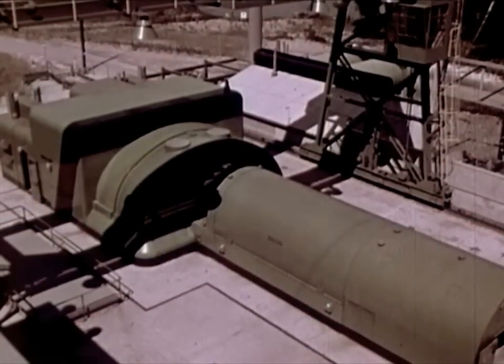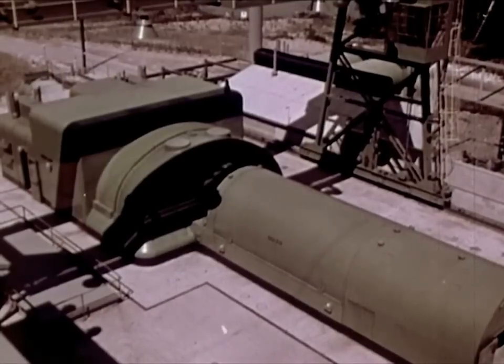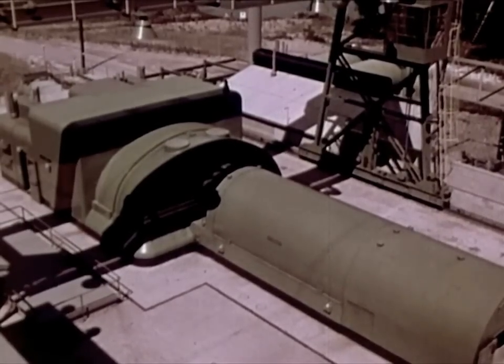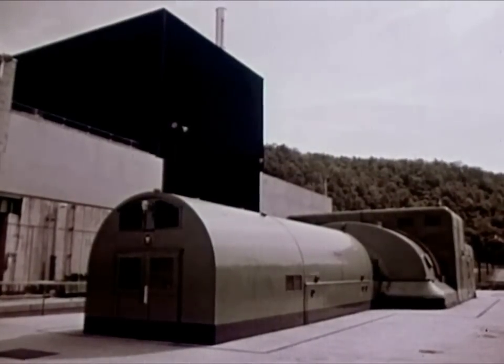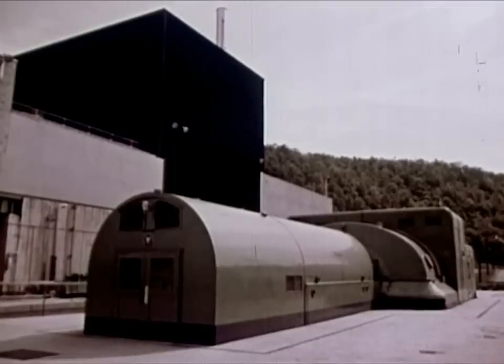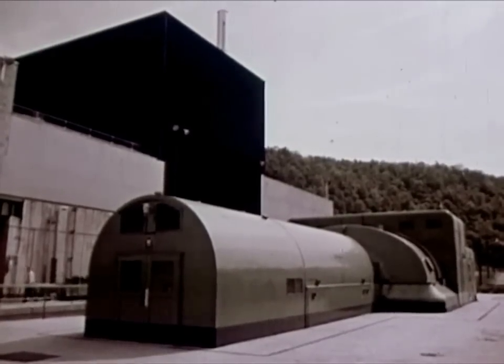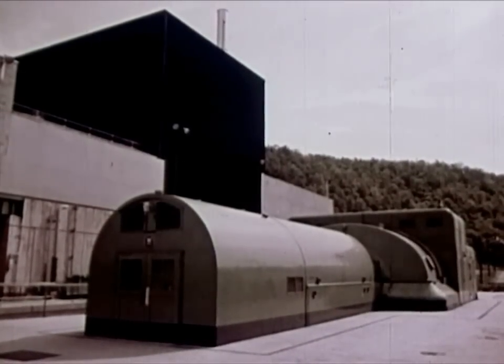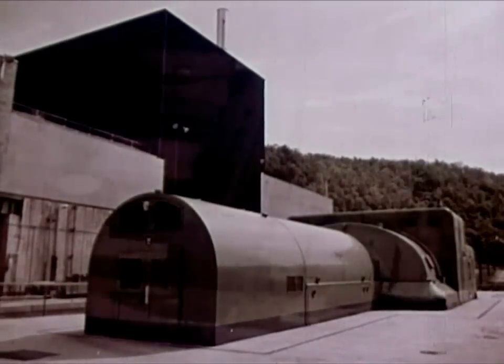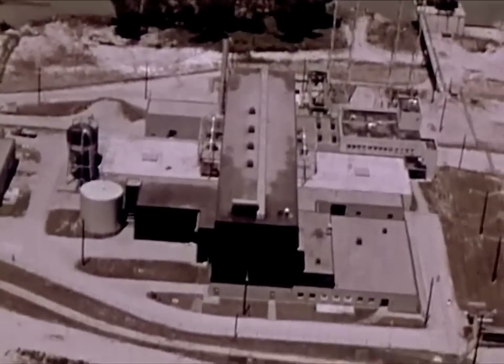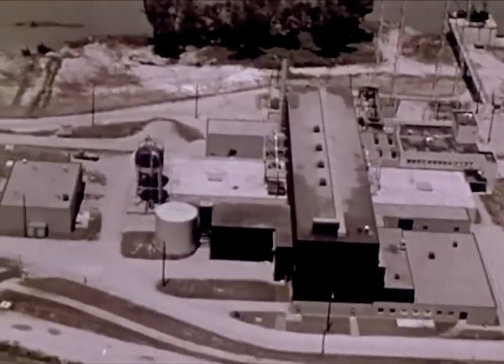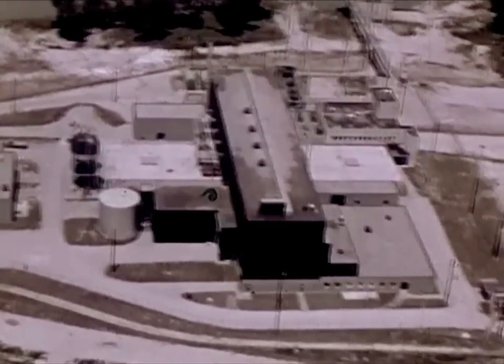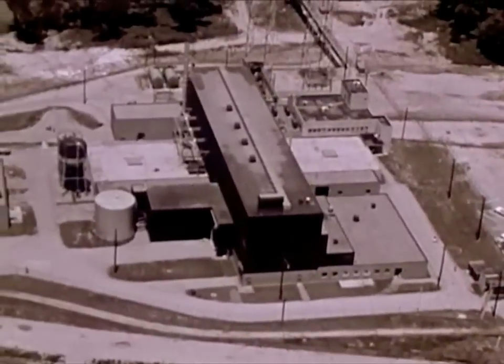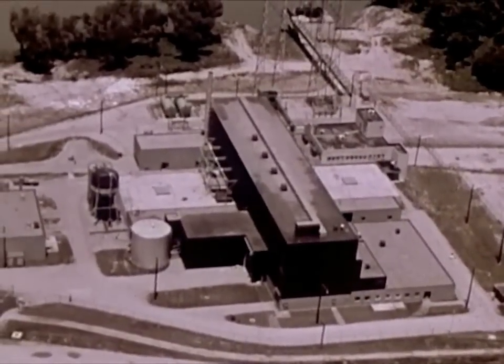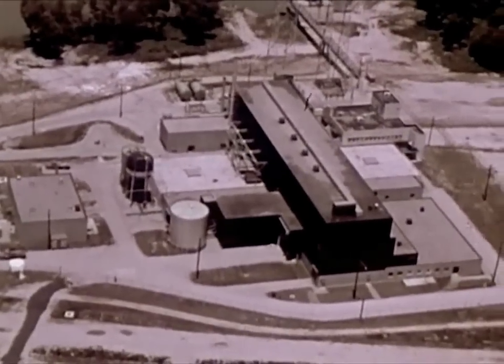The turbine generator is outdoors, unusual at latitude 41 degrees north in the United States. The shaft speed of the unit is 1,800 RPM. It is capable of producing 100,000 kilowatts in anticipation of future core developments. The Shippingport plant was completed and full power operation was begun approximately 3 years after the start of construction, which is in line with the time taken to build non-nuclear plants. The total elapsed time from the award of the design contract was 4.5 years.